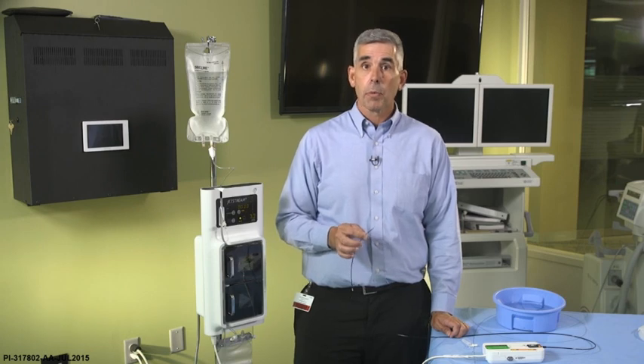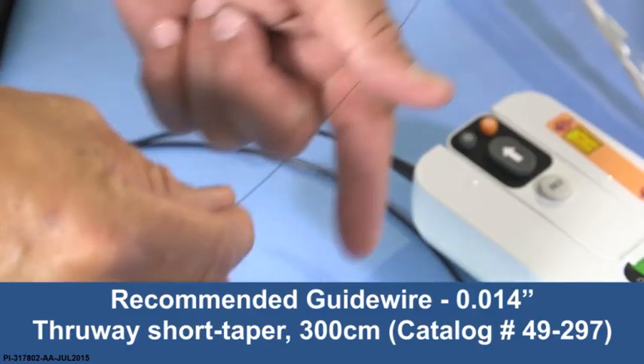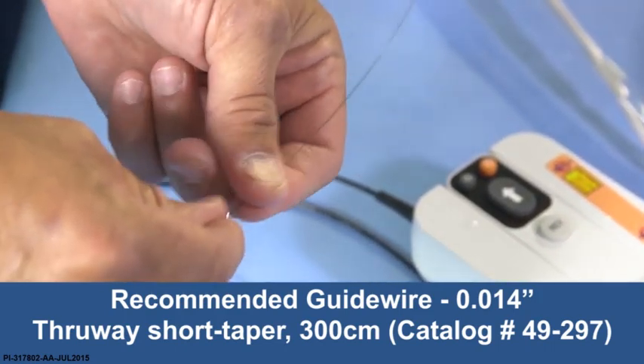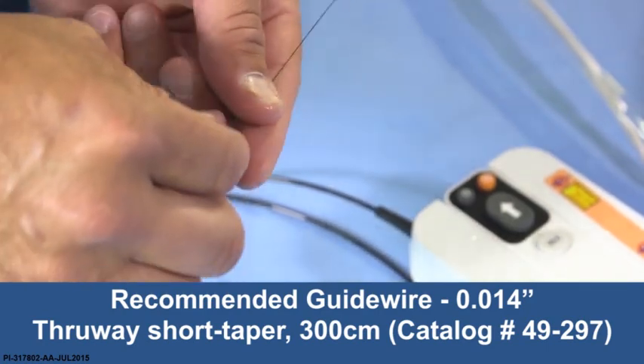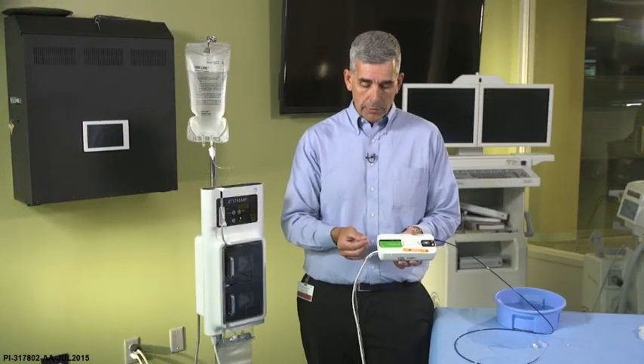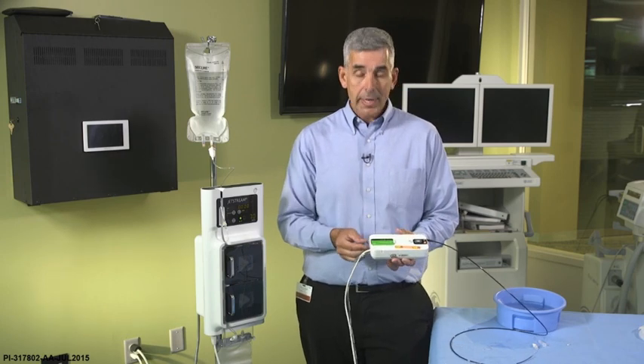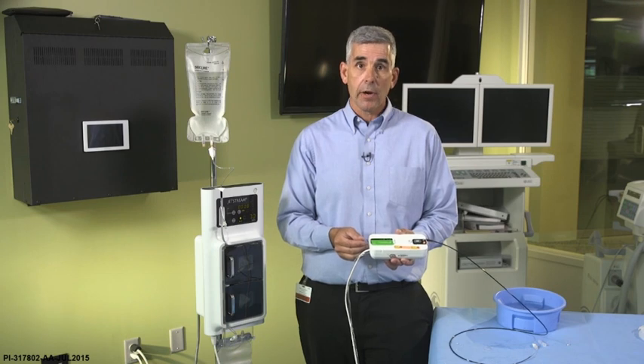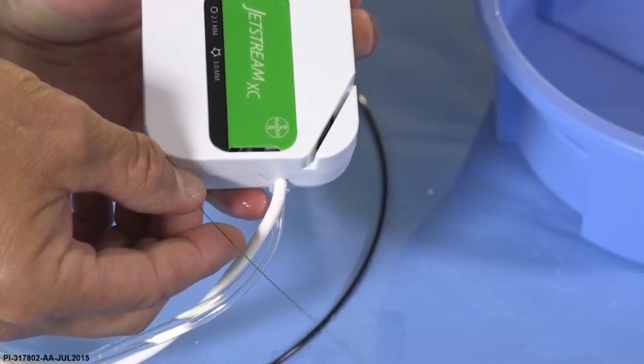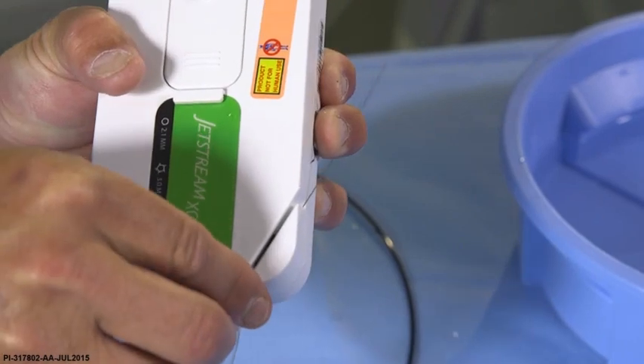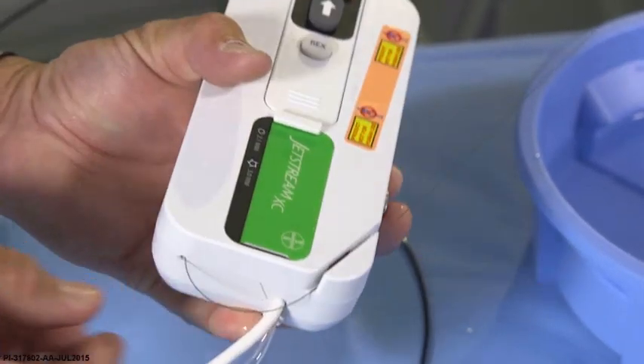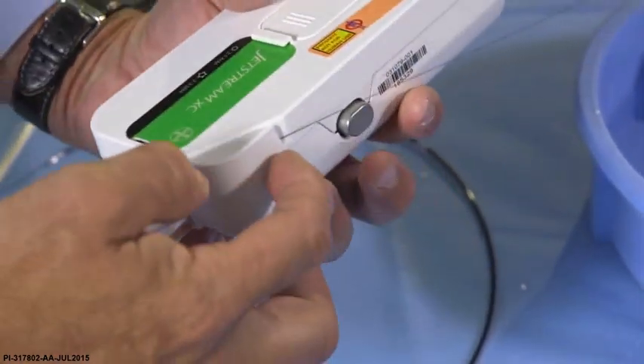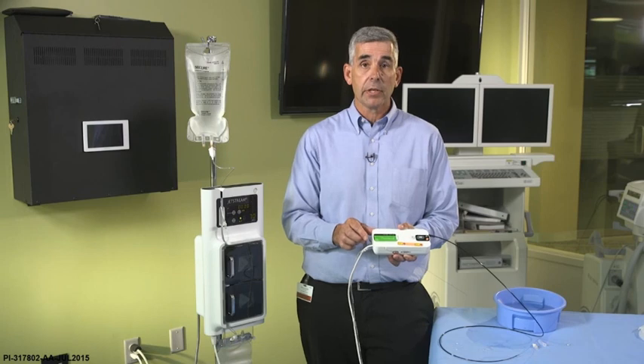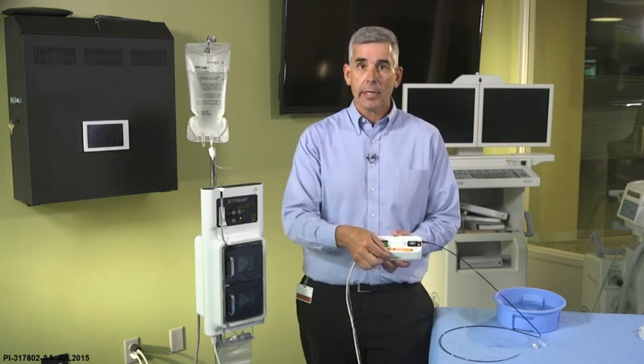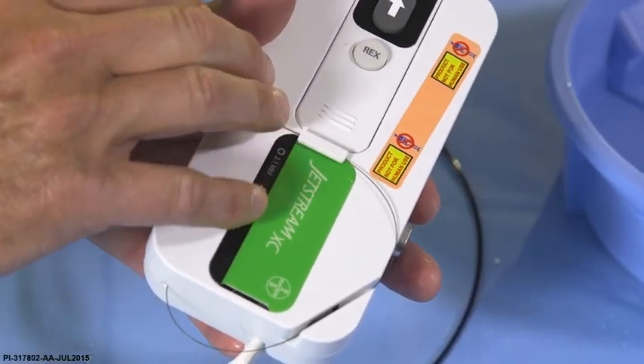With the guide wire in place, we will backload the Jetstream over the guide wire. Two of the wires we recommend using are the Thruway and the Jet wire, manufactured by Boston Scientific. With the Jetstream backloaded over the wire, you'll notice the wire exits the back of the pod. We now need to put the wire through the GARD, G-A-R-D, which stands for Guide Wire Anti-Rotational Device. We're going to grasp the wire from the rear of the pod, depress the silver button, and place the wire into the angled guard channel. Ensure that the wire sits at the bottom of the channel and is a tight loop between exiting the pod and being placed into the guard channel. The wire can be redirected if needed using the wire shelf on top of the pod.